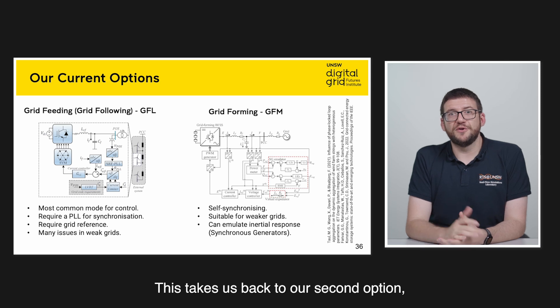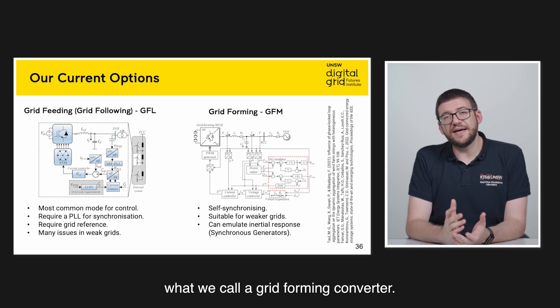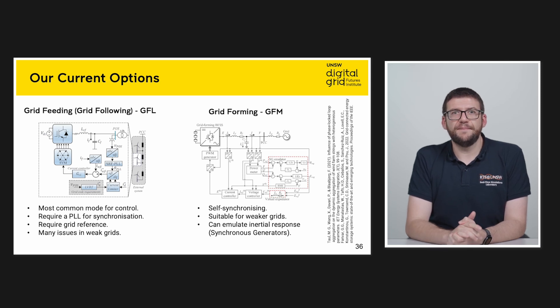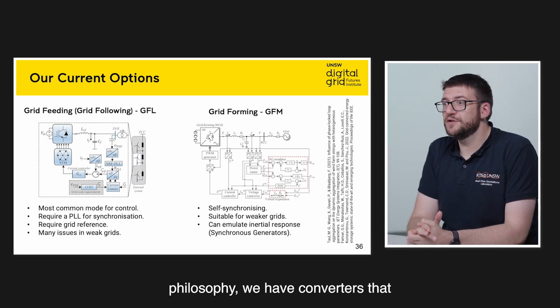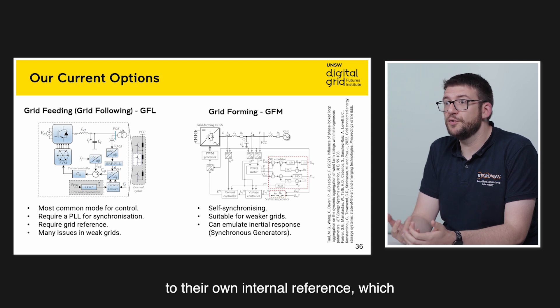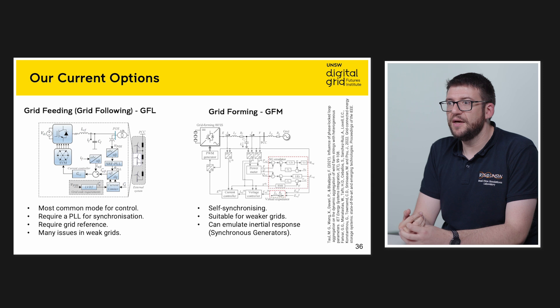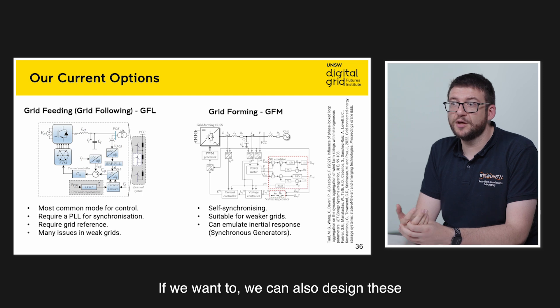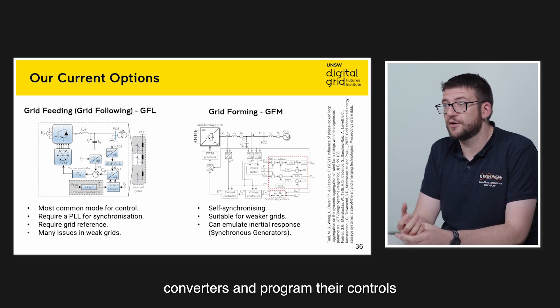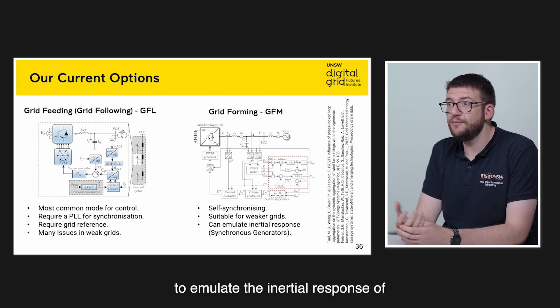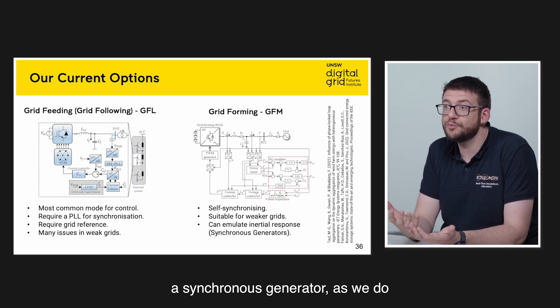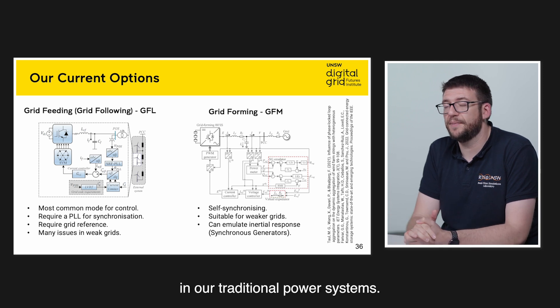This takes us back to our second option, what we call a grid-forming converter. By implementing a different control philosophy, we have converters that are able to synchronize by themselves to their own internal reference, which makes them well suited to weaker grids. If we want to, we can also design these converters and program their controls to emulate the inertial response of a synchronous generator, as we do in our traditional power systems.